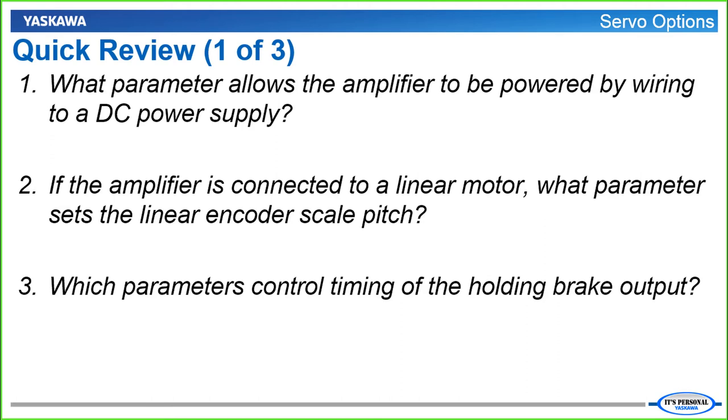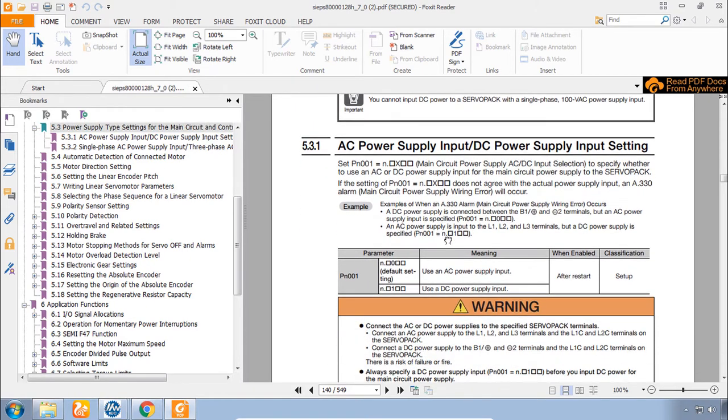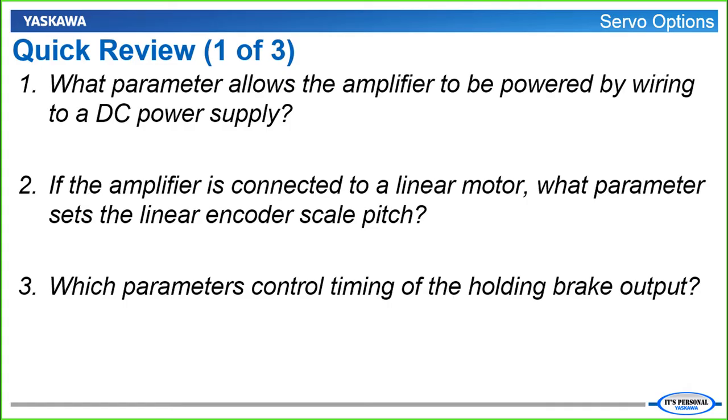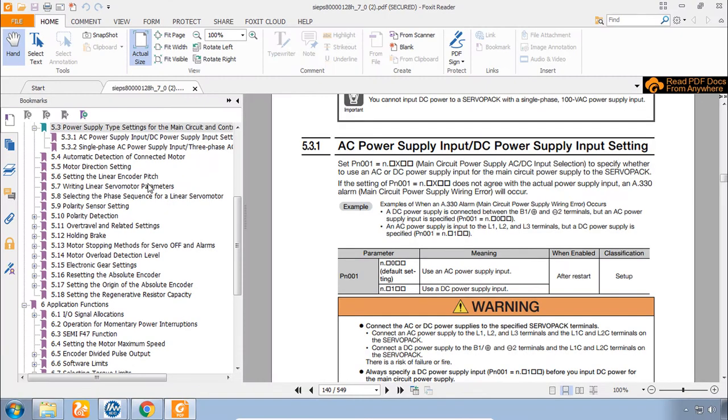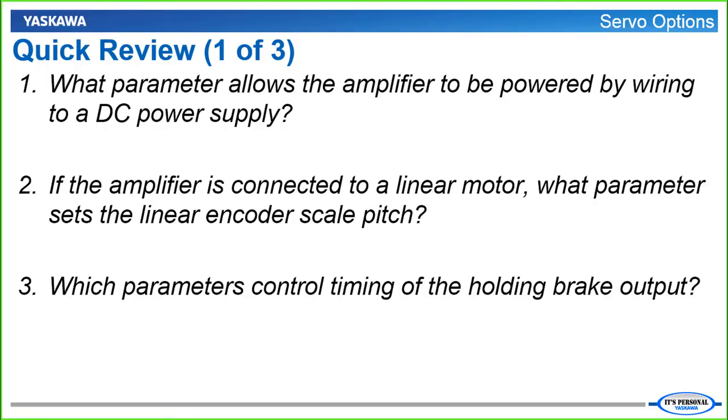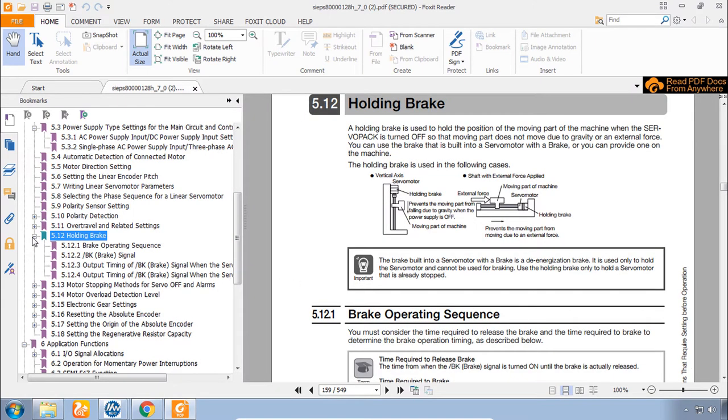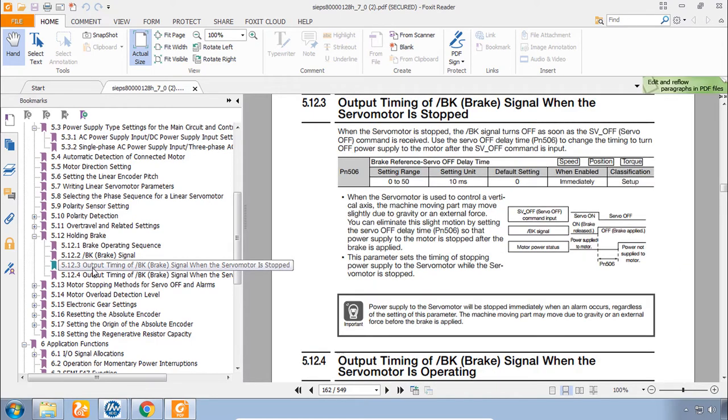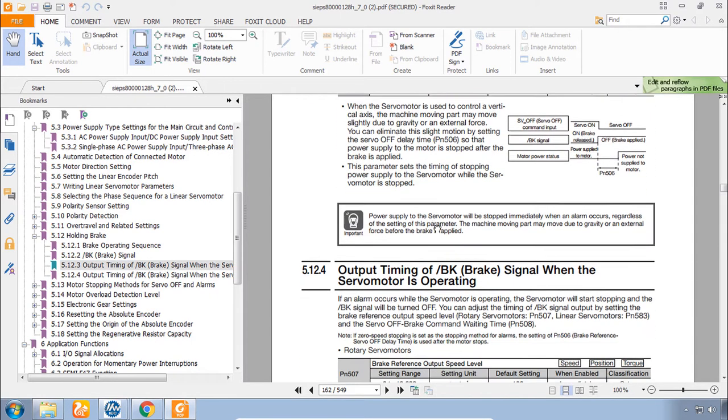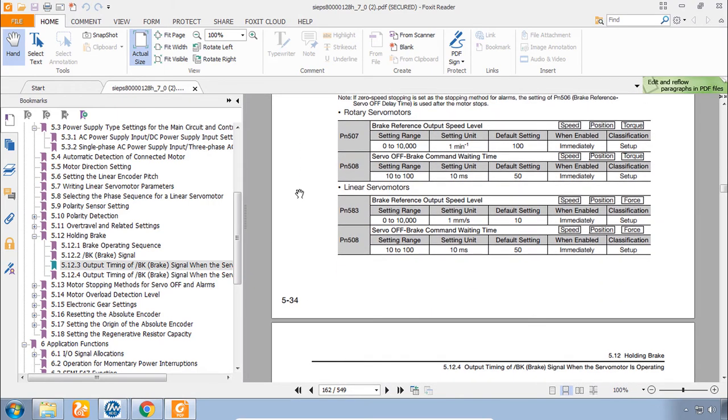Ok, parameter for DC power supply. That was in section 5.3. And the parameter is PN001. Question 2. Linear motor scale pitch. That was in section 5.6. Parameter PN282. And number 3. Timing of the holding brake. That was in section 5.12. And for holding brake you had to dig a little bit. And you see output timing. It's parameter 506. 507 and 508. And for linear motors there is a PN583.